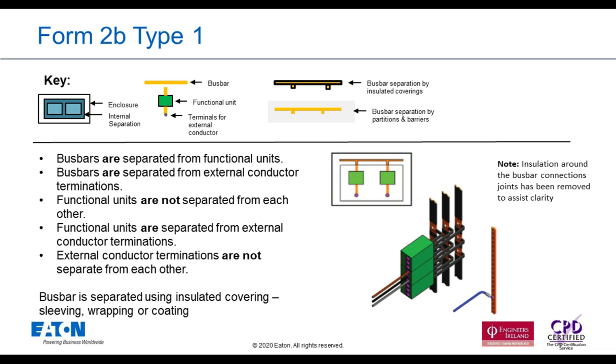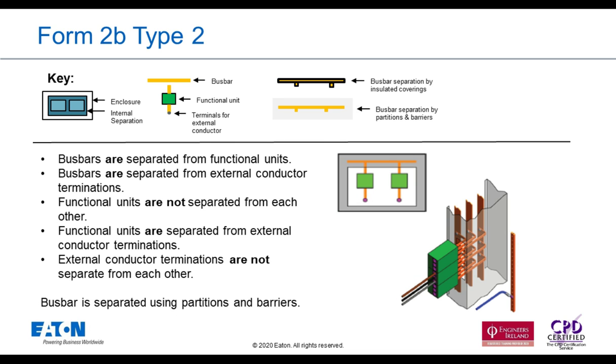But here we're separating the main bus bar from the outgoing terminals using some form of sleeving over the bus bar. So this sleeving could be insulation, could be powder coating. It could be heat shrink or something similar to cover the bus bar. Then you've got Form 2B Type 2. The only difference here is that rather than using some insulating material on the bus bar, we're using a barrier. So this could be a molding around the bus bar or some kind of metal or metallic cover around the bus bar.